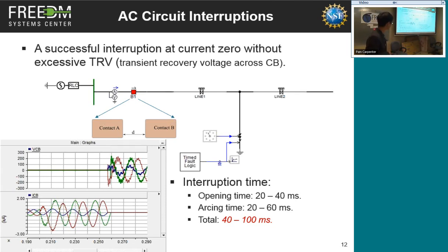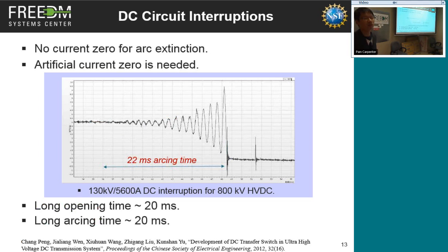That's what happens here. But in terms of total interruption time, because we care about how long it takes to interrupt this circuit, the first thing to do is you send out that trip signal. That signal comes into the circuit breaker. It takes 20 to 40 milliseconds to actually open the contact. And after that, you still need some time to try to extinguish that arc. You have to wait for current zero. And if at the first current zero you did not actually interrupt the circuit, you will wait for another one. So the arcing time typically is in the range of 20 to 60 milliseconds, and then the total will be 40 to 100 milliseconds. That's a long time, but that's what's happening in AC systems. It's acceptable. Then let's look at the DC system.